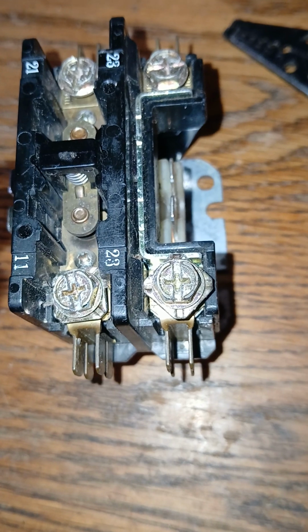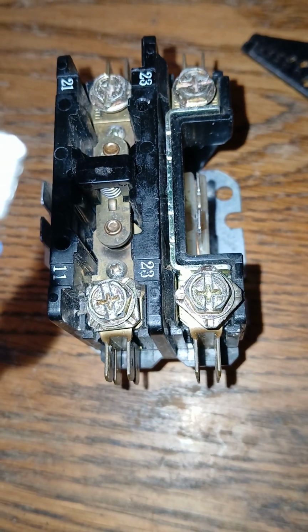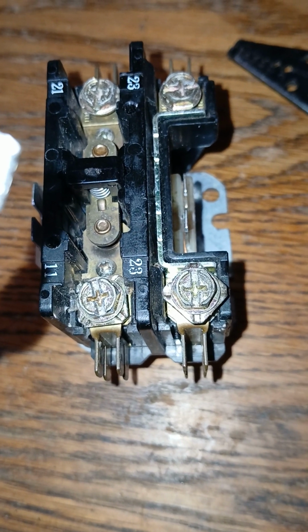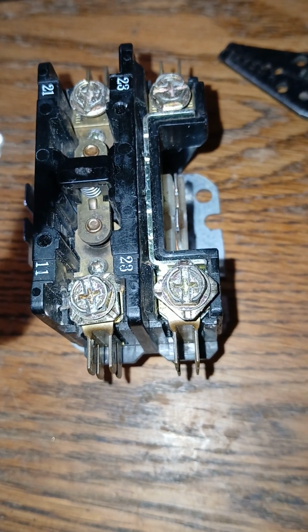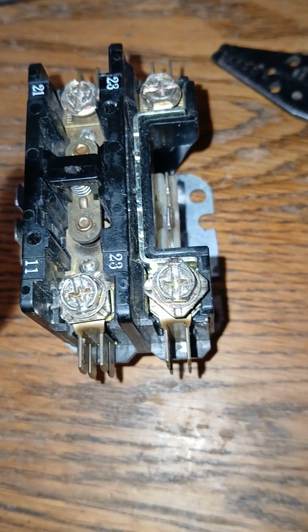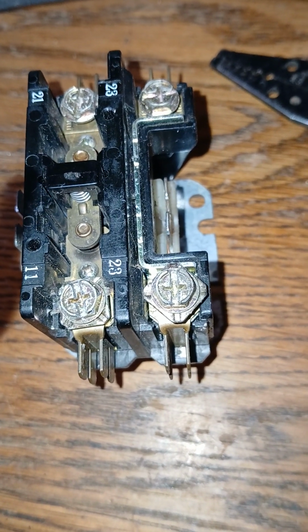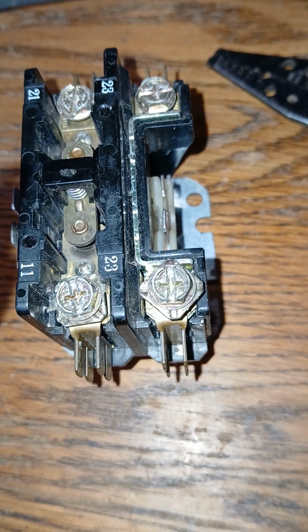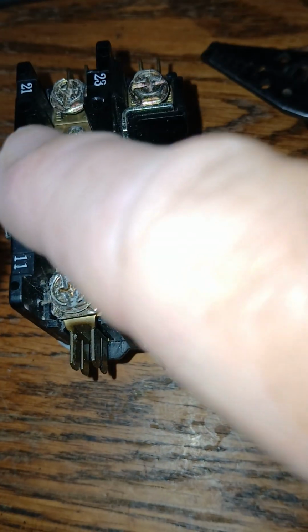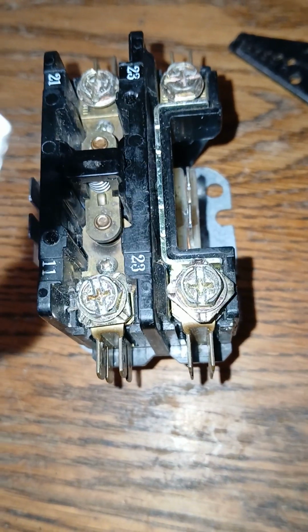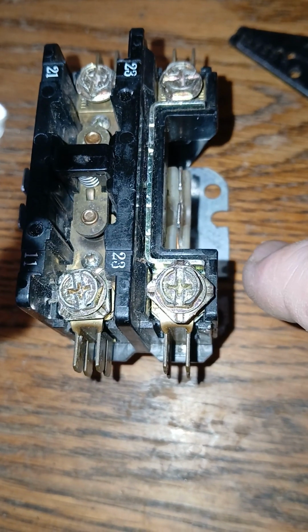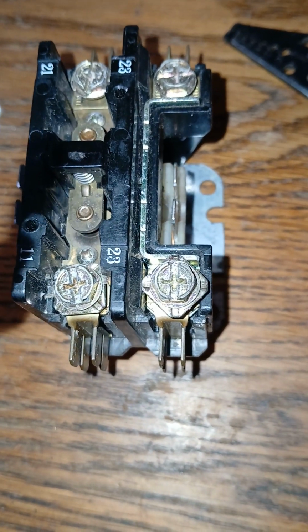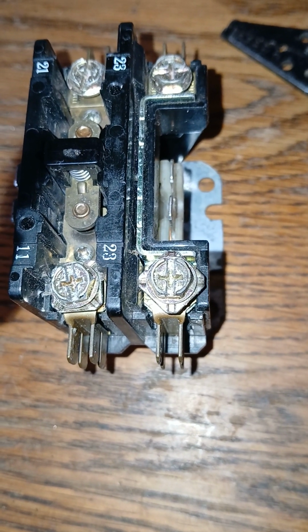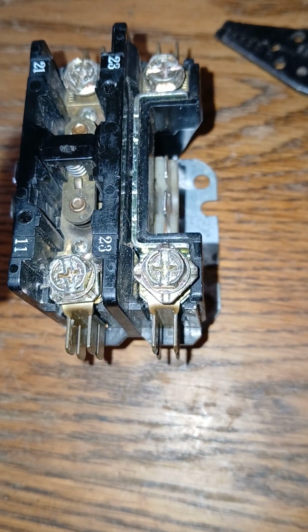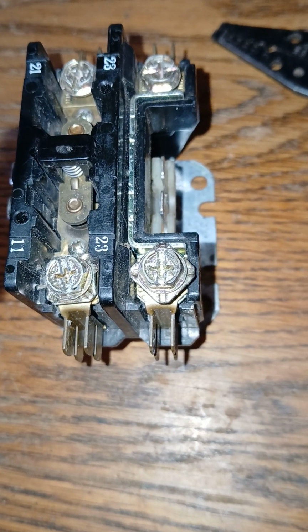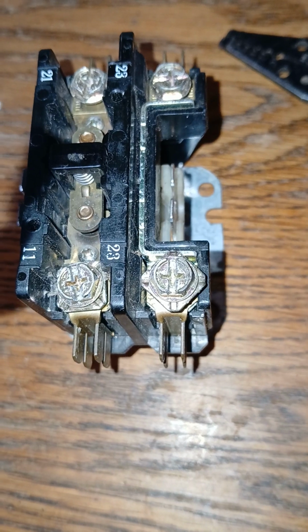And when one would say the criterion being met, what does this actually mean? This actually could mean your thermostat, say, if you're on the air conditioning mode and it satisfies the particular temperature that you're wanting to achieve on your thermostat, once that's satisfied, it breaks contact and this cuts off. So if it does not cut off, what happens then is the system just continuously runs, and as one can infer, the continuous charge of electricity without rest will eventually burn the motor up, whether that be a compressor or the condenser fan motor.